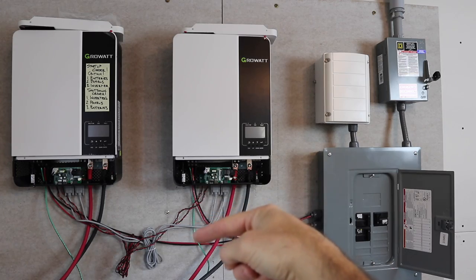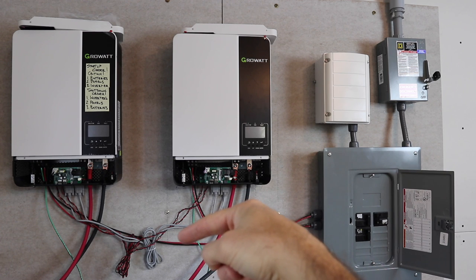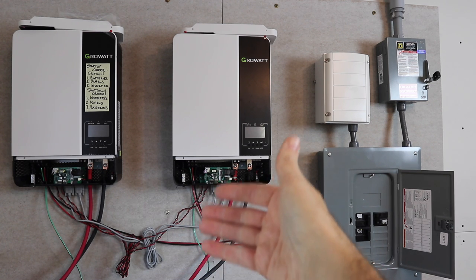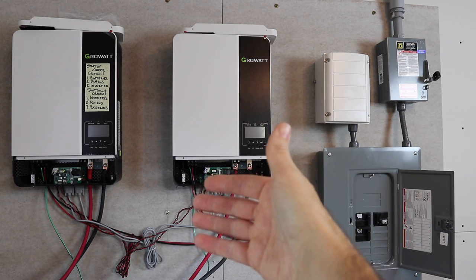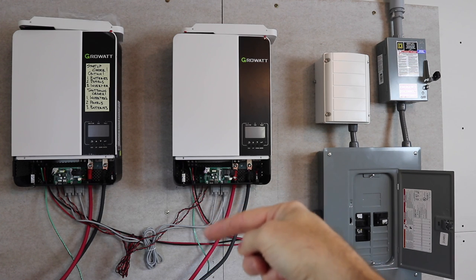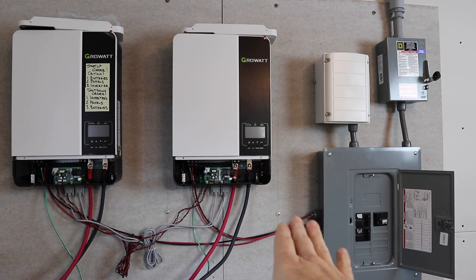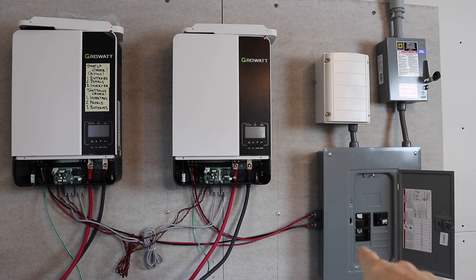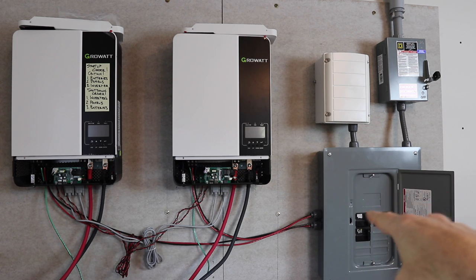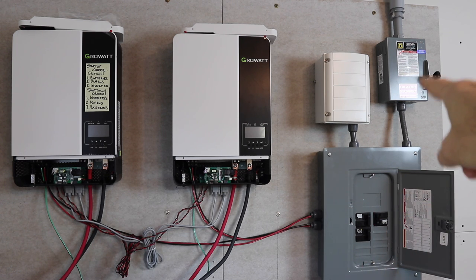So I'm paralleling these without my PV connected. And that's because my DC disconnect switch was not working properly. So I'm still waiting for that to come back in. But I believe I can still do this. I've got my breakers on my sub panel all on, so they are connected internally in that sub panel. But I have my safety switch off, so there's no power going to the house right now.